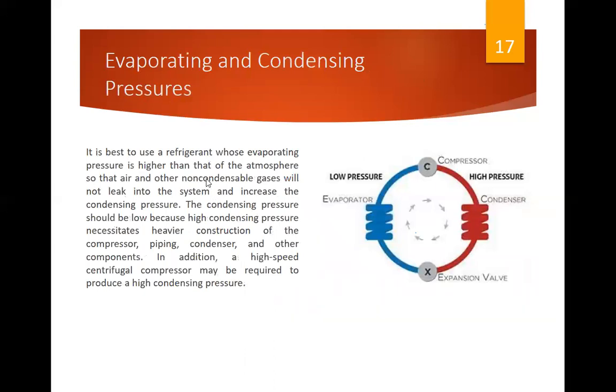Next is the evaporating and condensing pressure. It is best to use a refrigerant whose evaporating pressure is higher than that of the atmosphere, so that air and other noncondensable gases will not leak into the system. The condensing pressure should be low because a higher condensing pressure necessitates heavier construction of the compressor, piping, condenser, and other components. In addition, a high-speed centrifugal compressor may be required to produce a high condensing pressure.